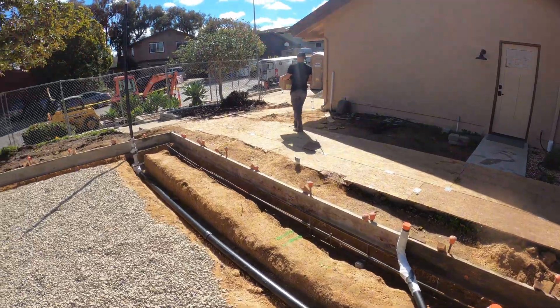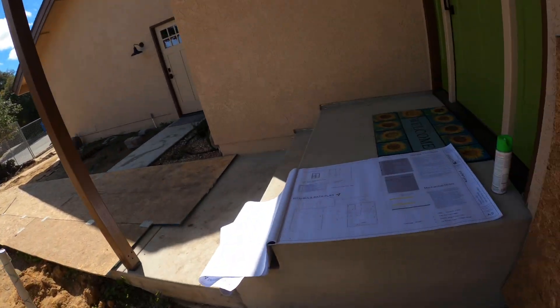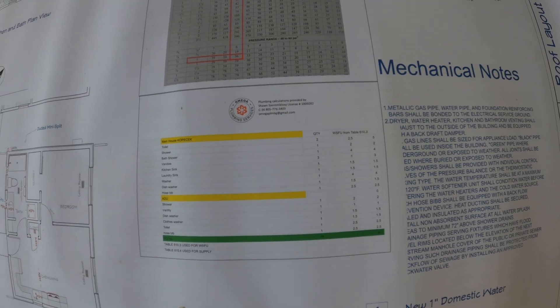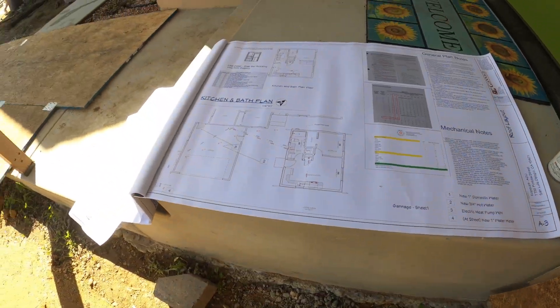Anyway, thanks for watching. If you have any questions about plumbing, let me know. I am not an engineer, I am not an electrician — I am a plumber. Although a plumber can do value engineering: when someone asks how many fixture units it takes for the water piping, or how many BTUs for gas piping, we are allowed to do that. To prove it — right here, we have plans that went through San Luis Obispo, there's my license, and those are the tables used to figure out the size of the water piping and gas piping. You don't need an engineer for everything; just get your plumber to do that.